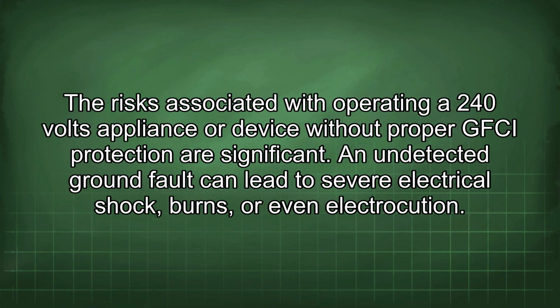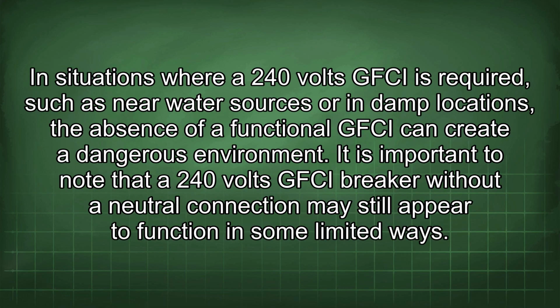The risks associated with operating a 240 volts appliance or device without proper GFCI protection are significant. An undetected ground fault can lead to severe electrical shock, burns, or even electrocution. In situations where a 240 volts GFCI is required, such as near water sources or in damp locations, the absence of a functional GFCI can create a dangerous environment.